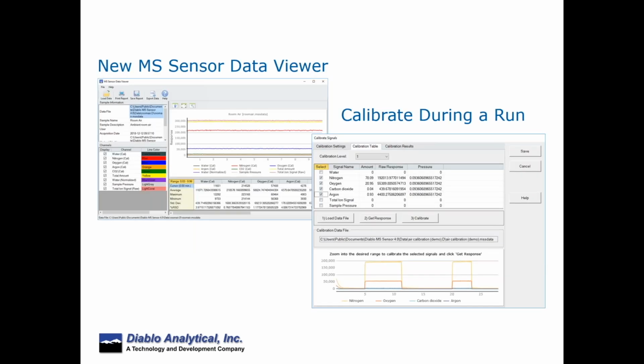But then while it's running, you can pull data from the system and look at it with the MS Sensor Data Viewer. And you can zoom in on different components. You can eliminate some or look at all the components at once. And then you could take a region of that data and you can do a calibration during the run. And that's what we show in the lower right there. And you can then update your calibration during the run. Calibration is very straightforward. It's an external standard calibration, which we're used to, and you can do an external standard calibration, and then you can apply it to that component in your sample matrix that's coming out of your process.